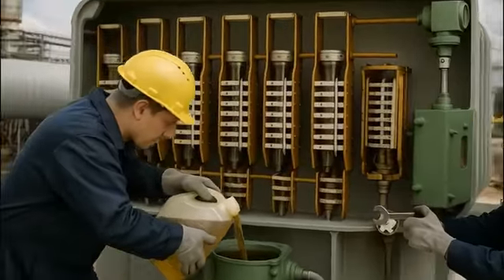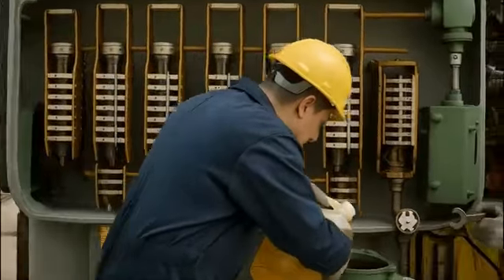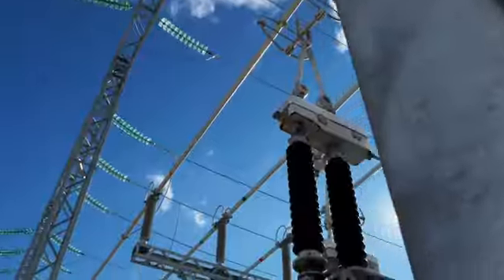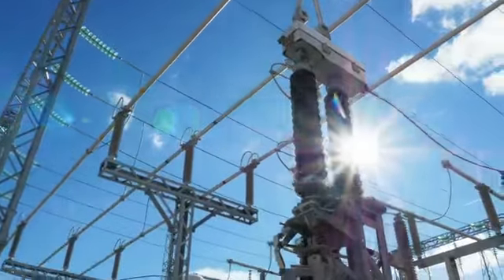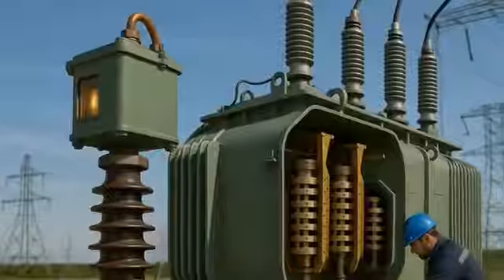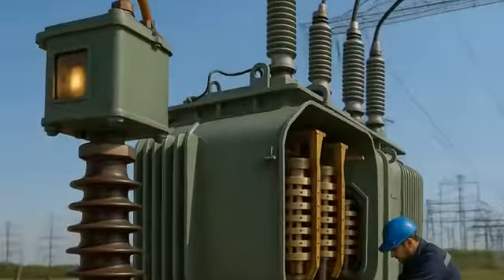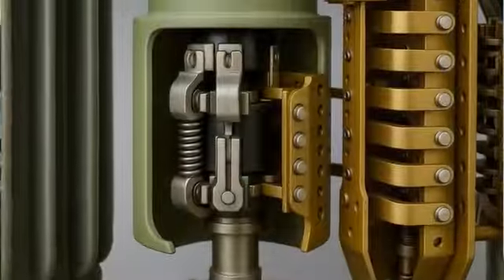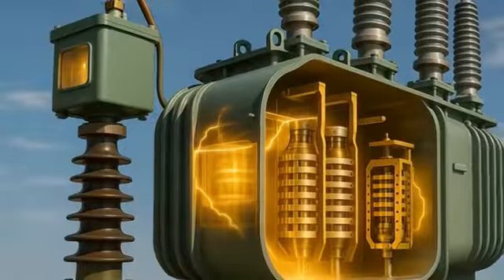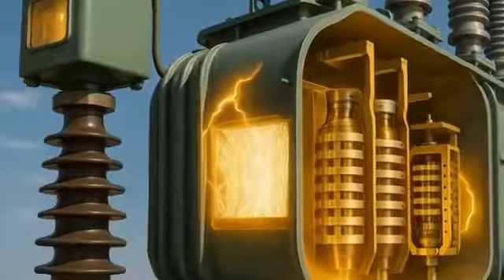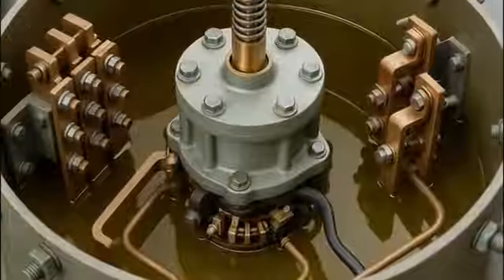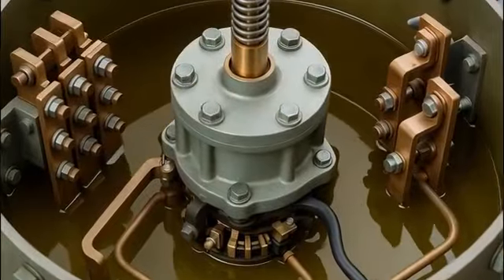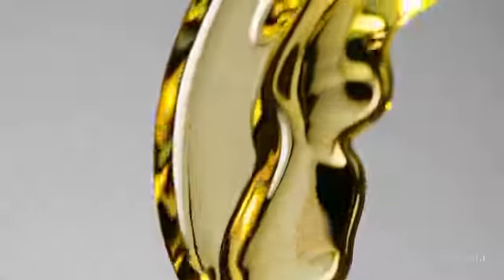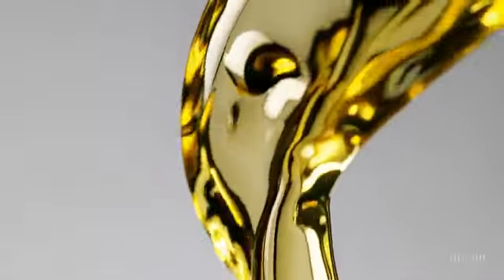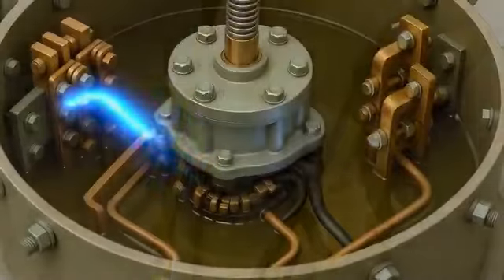There are two types of design for onload voltage regulators, depending on the oil system features. In the first case, a tap changer contactor is located in a separate tank on the insulator, and in the second case, the device is located either inside the transformer tank or in a separate tank with transformer oil contained. In this case, the onload tap changer oil is responsible for quenching an electric arc that may occur when the contactor switches to operating position.